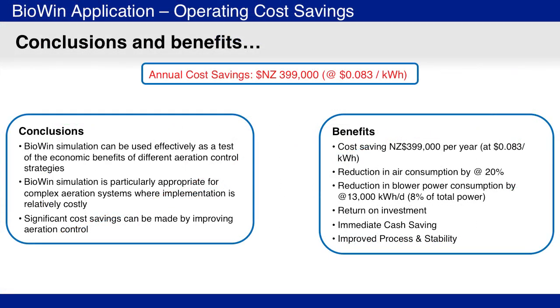The benefits of these findings to the plant owner included the following points. The simulation approach was a cost-effective method for selecting an improved aeration control strategy for implementation. Once the improved aeration control strategy was implemented, total air consumption was reduced by 20%, resulting in a significant reduction in power consumption, which in turn translated to an annual cost savings of nearly $400,000. The improved aeration control strategy identified by the BioWin simulations resulted in rapid return on investment and also improved plant effluent stability.